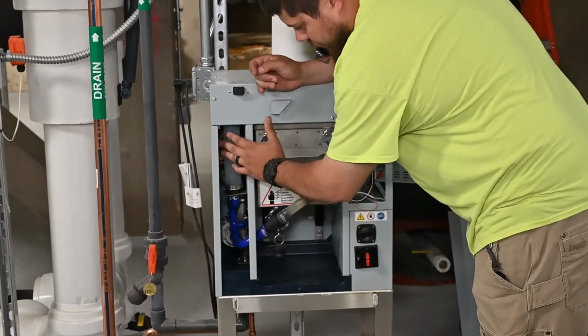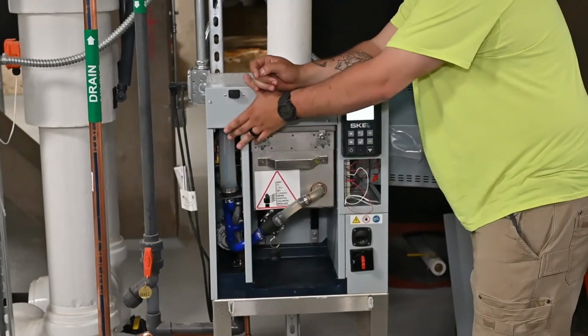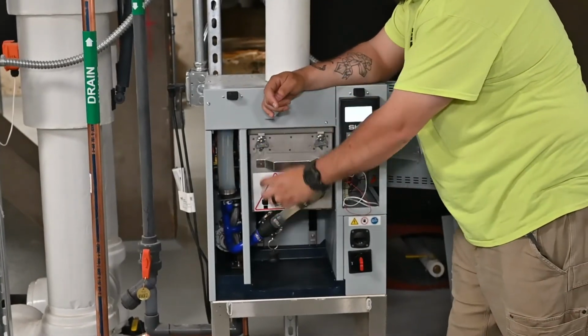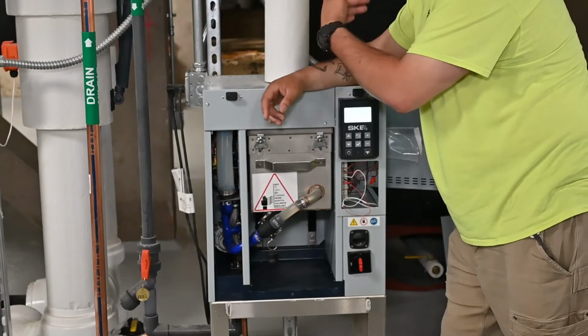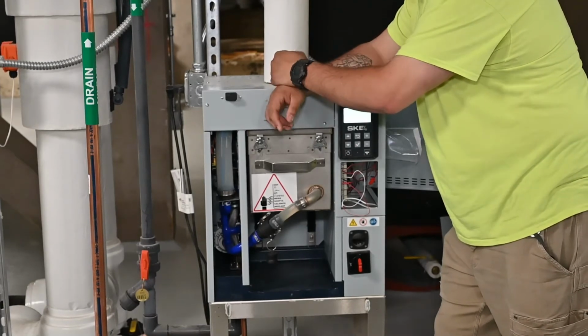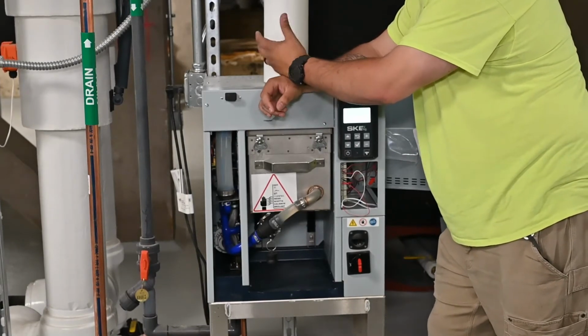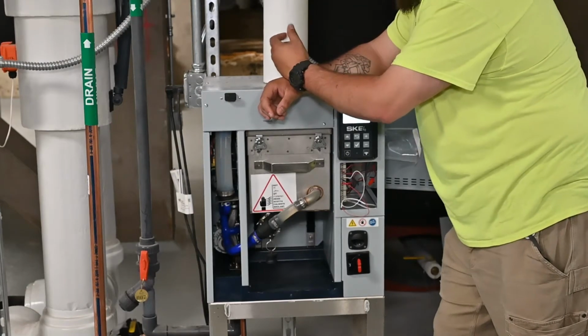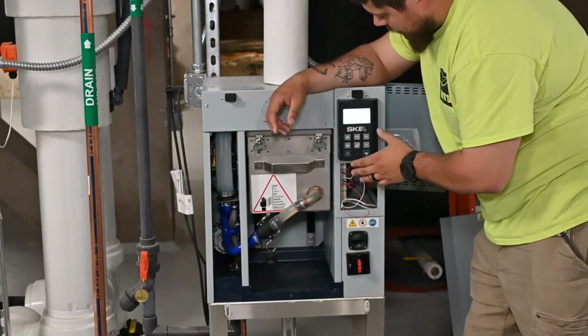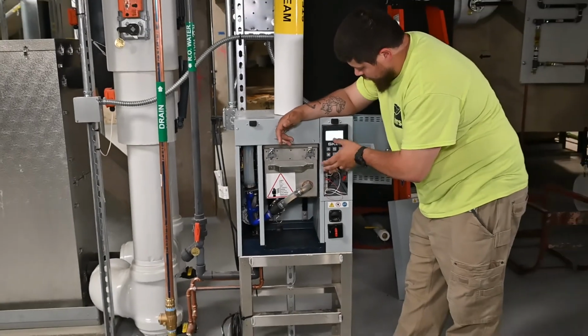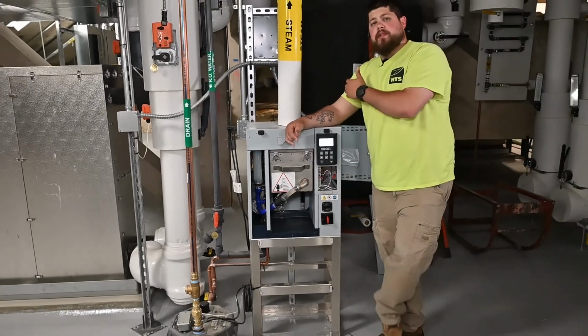On the left side here, you can see this is where your meter is for the leveling of filling on the tank. You have 3 probes in there. One's really low down, one's up in the middle area, and one's up high. Obviously, there's a low and a high, and the middle is where you want to be. There is a display here. There's not much that would have to get done here, but it will show you what state it's in, what kind of demand it's in, and how it's operating.